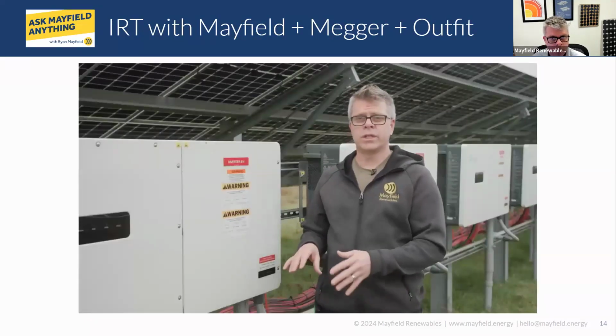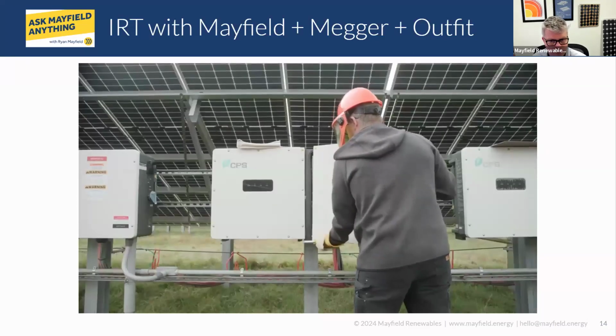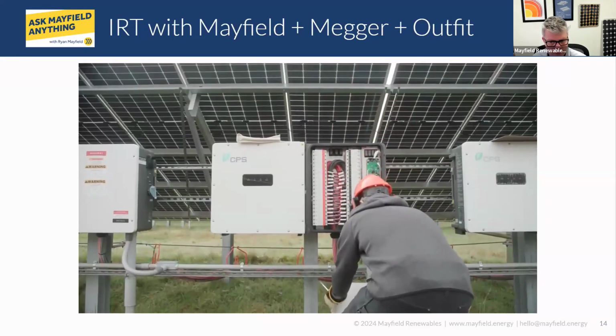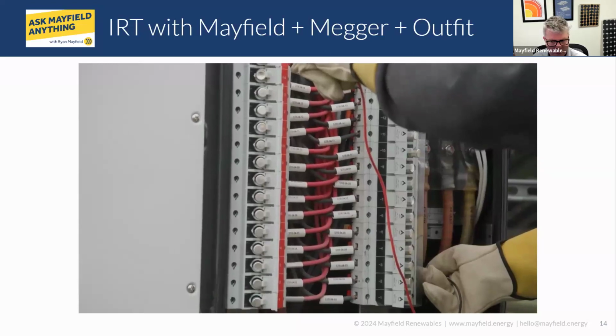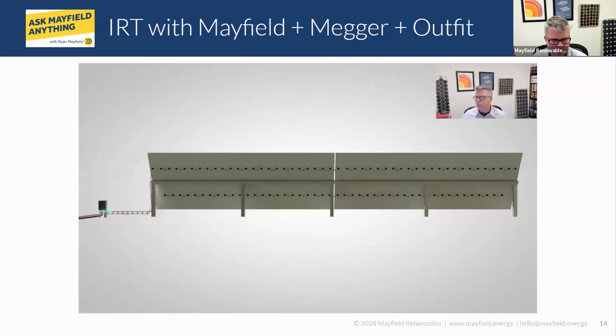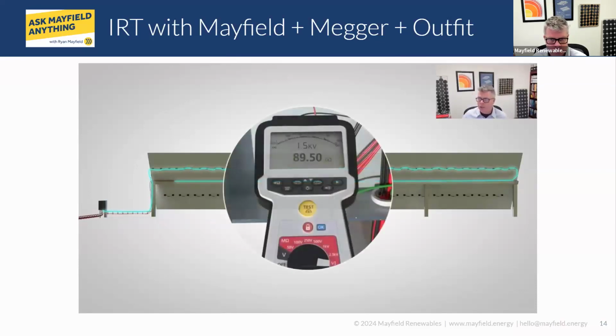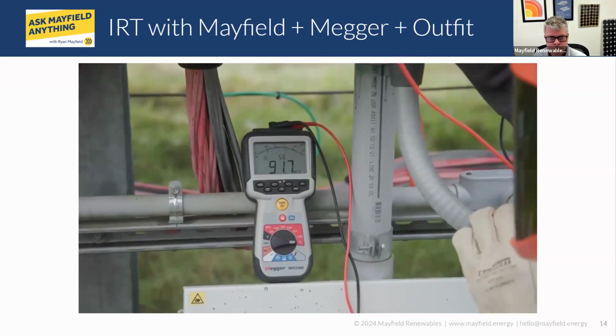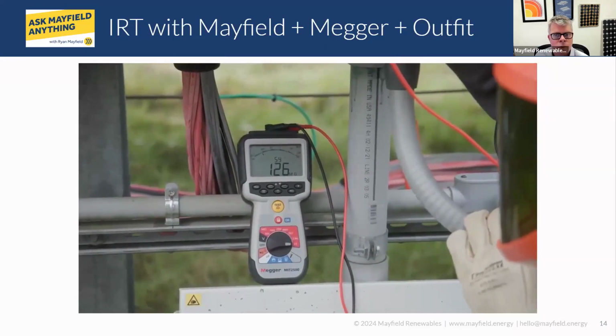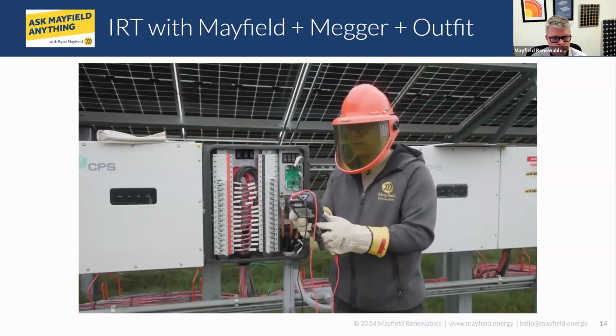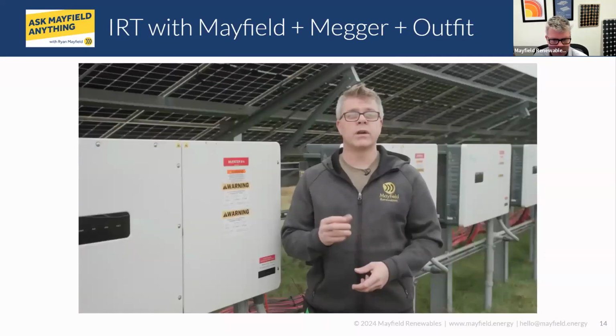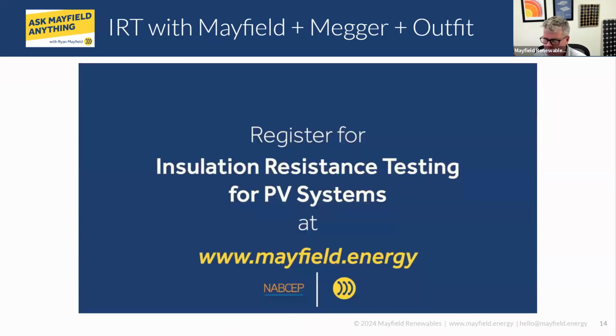What we're going to do is open up, in this case, our inverter, and we will isolate the different circuits. We will use our insulation resistance tester, put voltage on that wire or circuit that will pressurize it. If there's any bad parts of the wire, the electrons will find a way to ground, and the meter will record that. We're going to be able to read the meter, look at the actual value of that resistance, and make a determination if the conductors are in good shape or not.